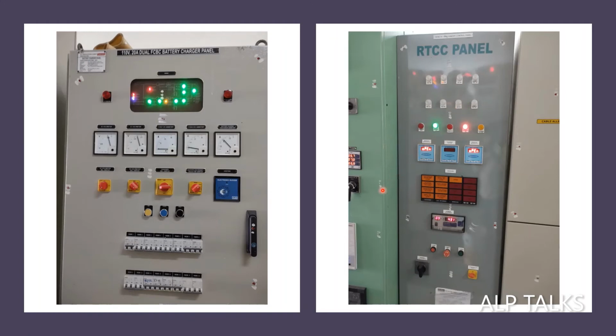Generally in solar power plants we have a power transformer in most cases. The power transformer will take care of all the voltage variations, so there is no need of a separate tap switch on the inverter duty transformer. That's what I said in the last picture, because RTCC itself will take care of all the voltage variations. Very rarely, you can check with solar power plants, they may not operate it even once in a year. So we can eliminate the tap switch, which makes the job very simple, easy, and failure free. If the RTCC or OLTC is not there, and the inverter duty transformer is connected directly to the local 33 kV grid, then we may need an off-circuit tap switch with more range.